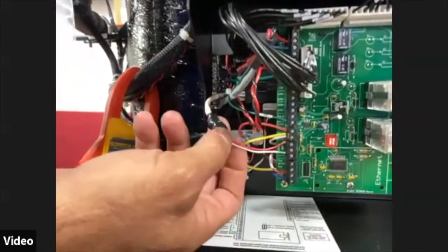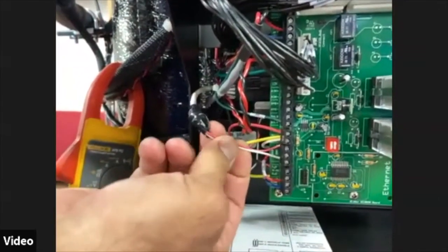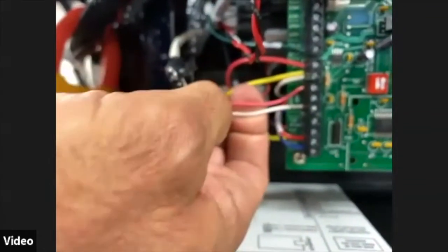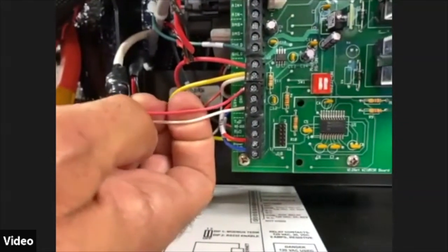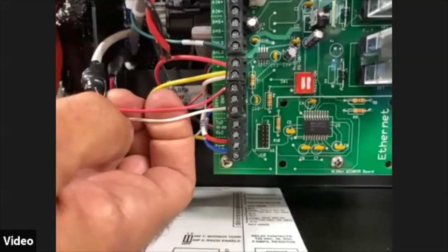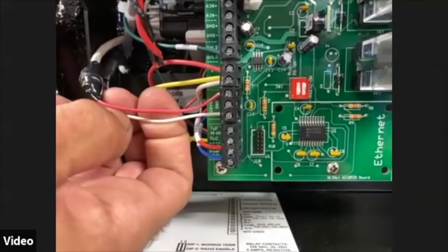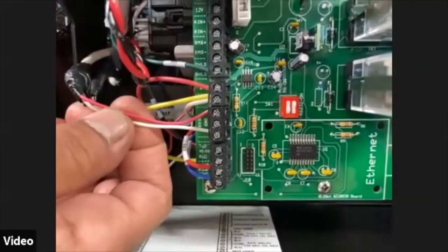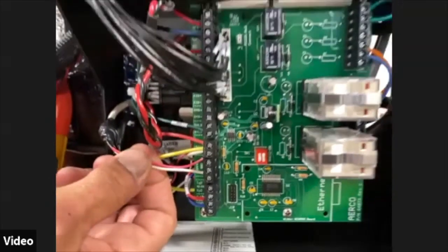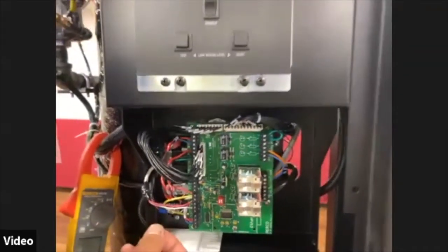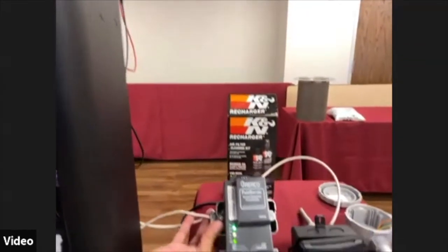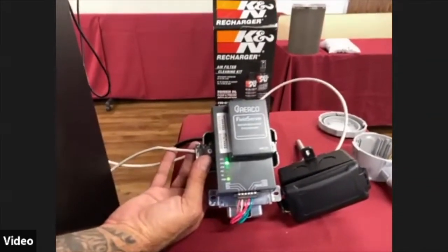And this is also where we connect our RS-485 communication wiring. So this would be our daisy chain if we were cascading multiple boilers together. In this case, we're just using the one today. So our RS-485 is hooked in here from boiler 1, and that goes over to our FieldServer ProtoNode gateway.